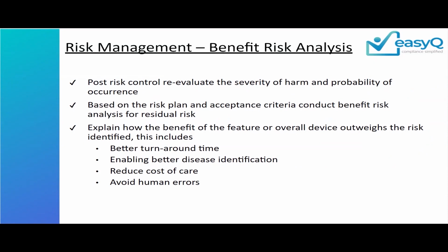Okay. Now, as I said, you typically cannot make your risk zero. If you make a risk zero, it's basically that that feature does not exist. So you identify risk, you did your analysis, you identified a number of risks. Then you did your evaluation to understand which risks fall where, high, medium, low. Then you put your controls. After controls, some of the risk will remain where it is based on what kind of controls you have put.